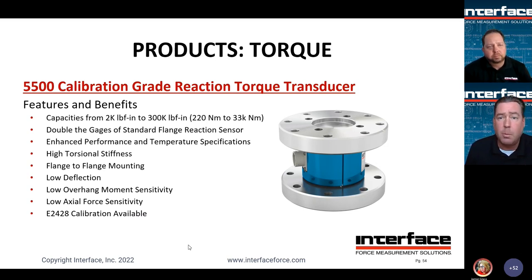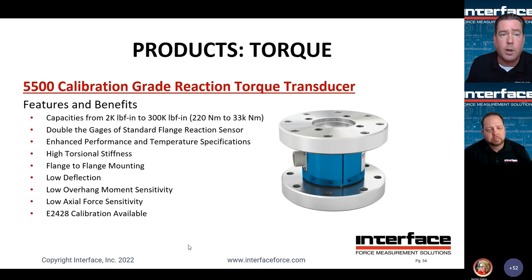This is a newer product feature here on the torque side, the 5500 series. We've taken our 5400 series and done much like we did with the column. You'll see a common theme here. Double the number of gauges, again trying to reduce sensitivity to off-axis and eccentric loading. Essentially, we've also, on some capacities, doubled the number of mounting holes to make sure there's sufficient clamp force to eliminate the possibility of any slippage in the calibration.